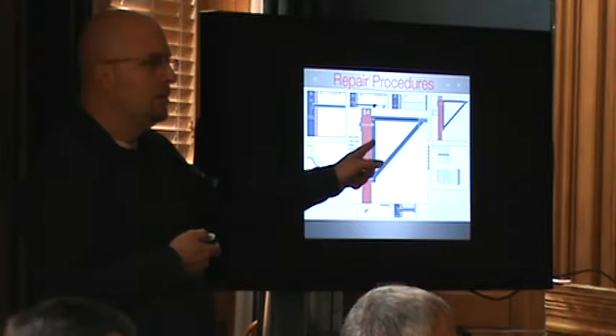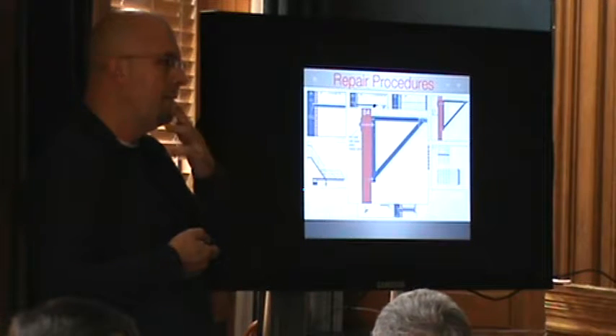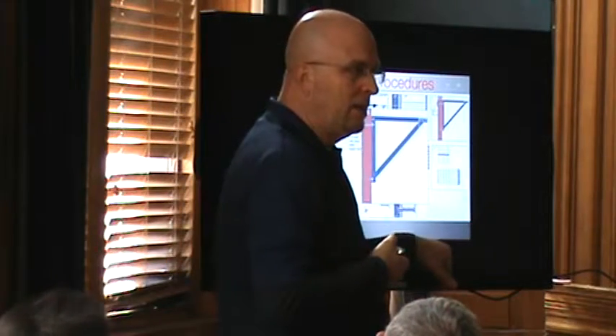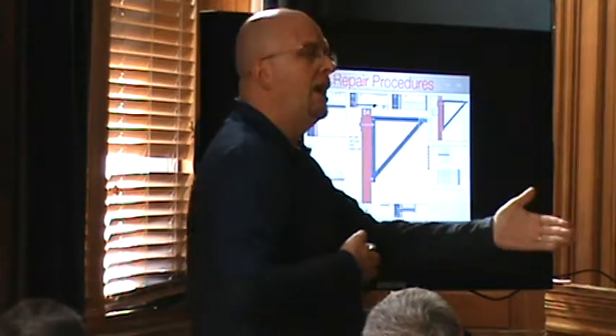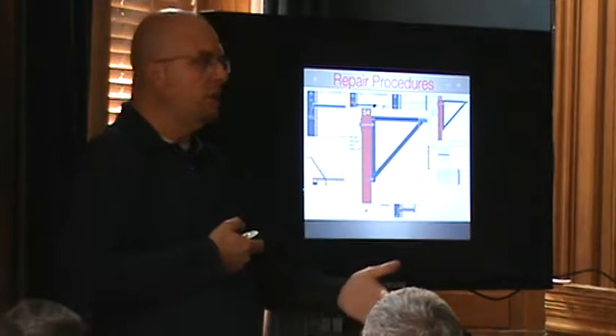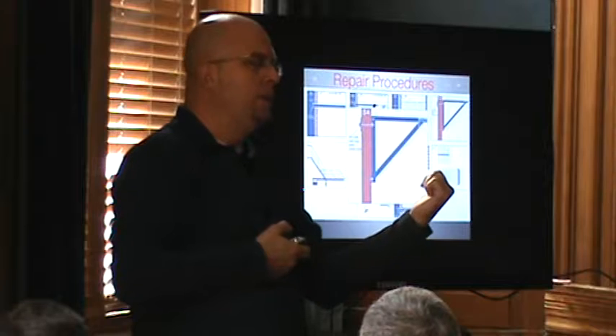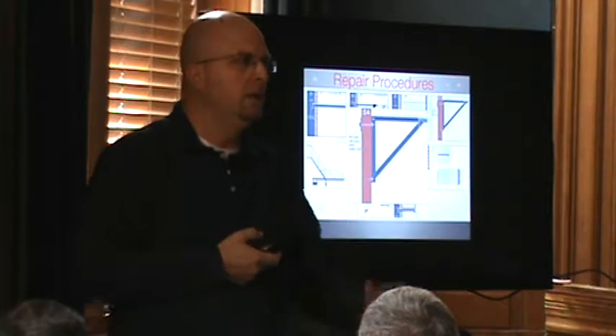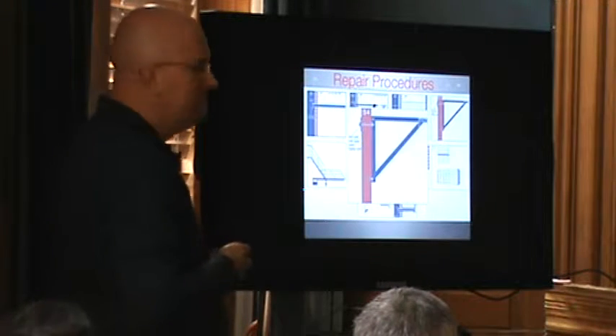Now, are they bound by the 5-year load test going forward after that repair? 5 years later, they have to load test it again. If they certified it at that time, 5 years later, there's no load test because you're choosing other evidence of strength. And that could last 15 to 25 years if you keep maintaining it, because the city's going to always ask you, what are you providing me as other evidence of strength? Well, 10 years ago, we certified, we refurbished it completely. We didn't just spot repair, we refurbished. Oh, okay. And they'll accept the documents from the engineer.